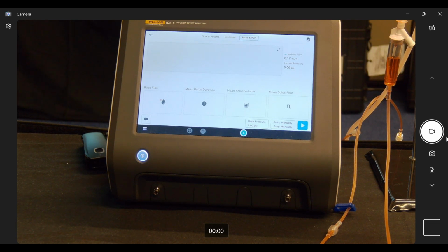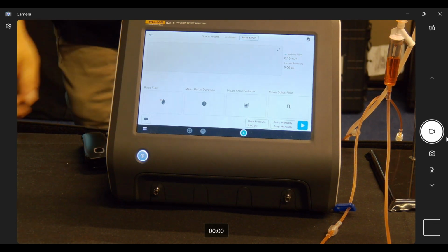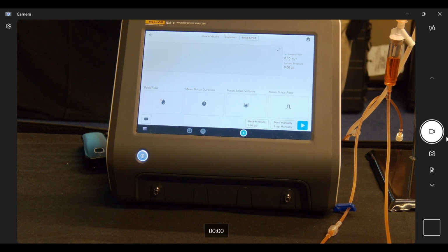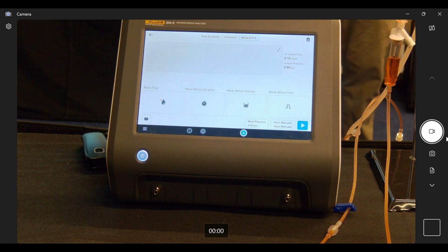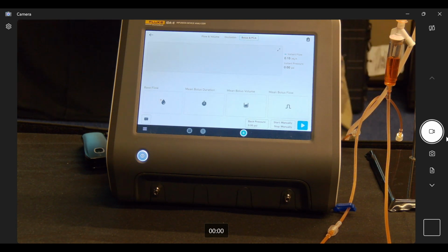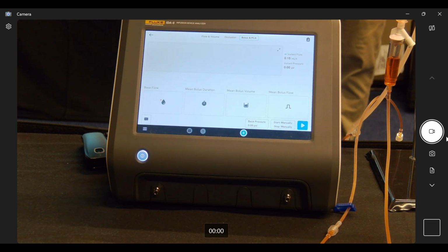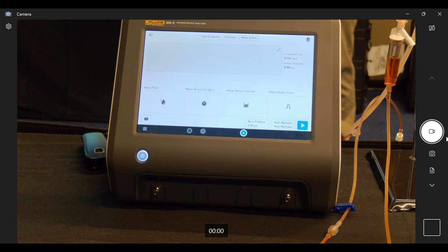Let's talk about a syringe pump for a second. How do we calibrate most of our syringe pumps? We've got a strain gauge, we put it in to make sure that linear actuator is spinning at a known rate and at a certain pressure. And then we put in a bunch of cylinders to determine what size syringe we put in.